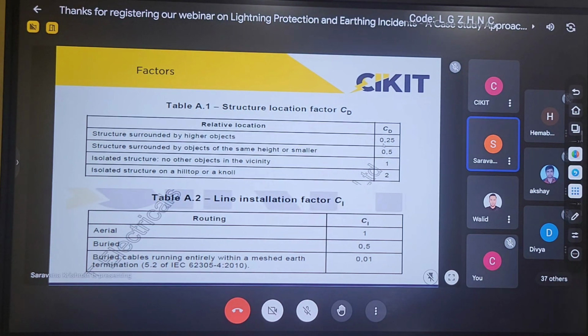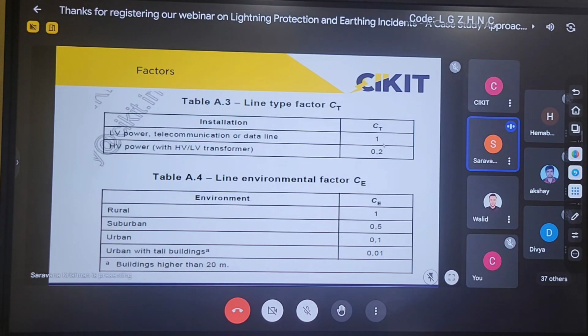The next one is the line type factor. How does the line type make a difference? If I am taking a high voltage line, then before the transformer, the first component we will use is the lightning arresters, that is, high voltage lightning arresters. If lightning strikes any of this power line, at the point of entry itself we will provide a surge arrester or high voltage lightning arrester for diverting the surges to the ground. Since we are providing a separate surge protection device for diverting the surges, the risk value is lower in high voltage lines, whereas in low voltage lines we won't have any separate surge arresters. So the risk will be higher if I am taking LV power, and lower if I am taking HT power. The next one is the line environmental factor.